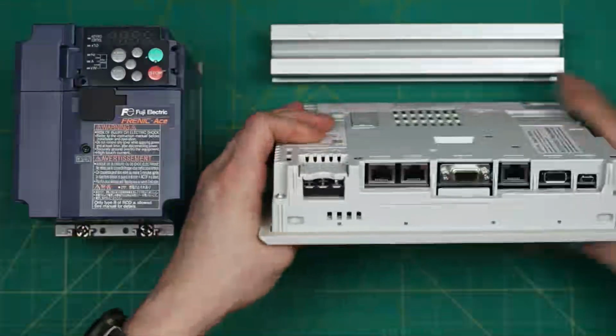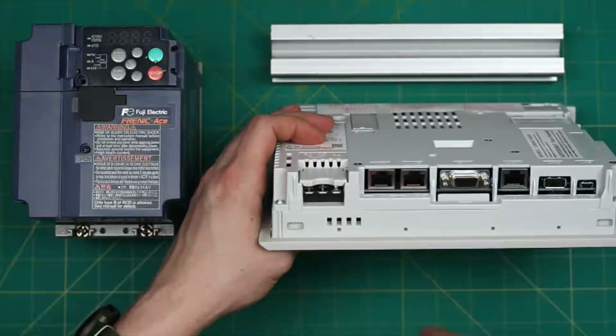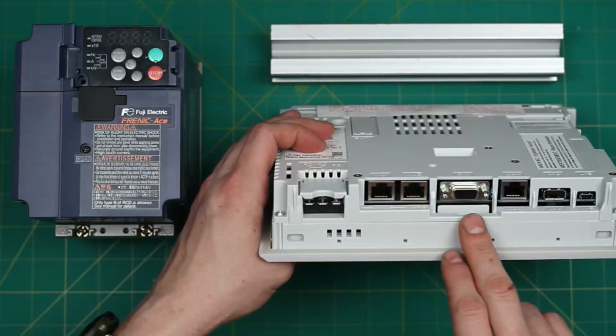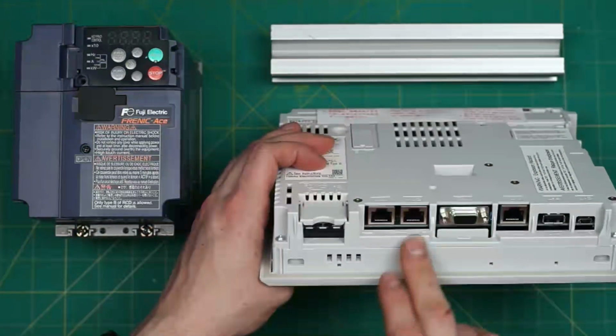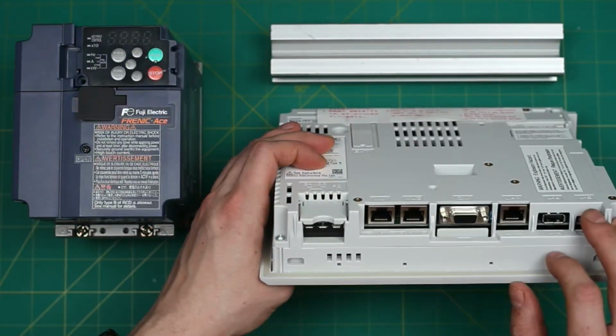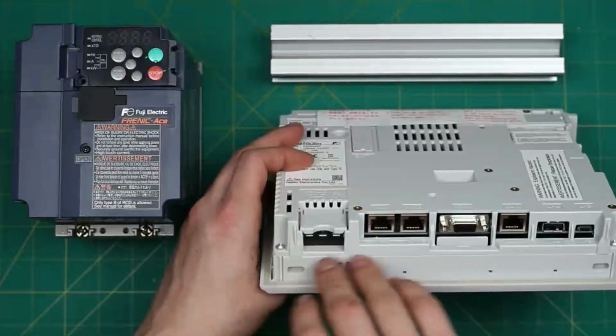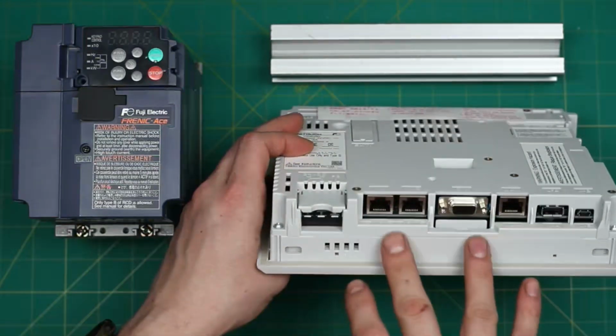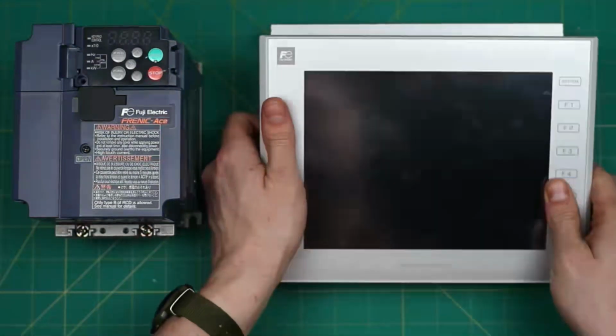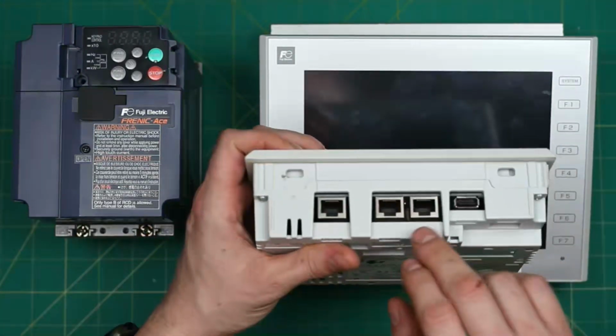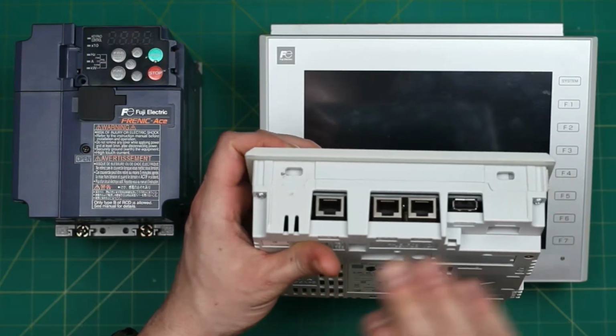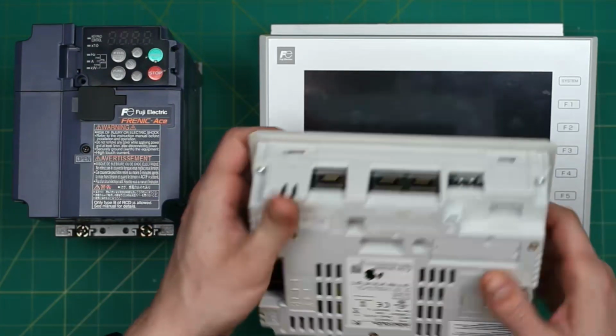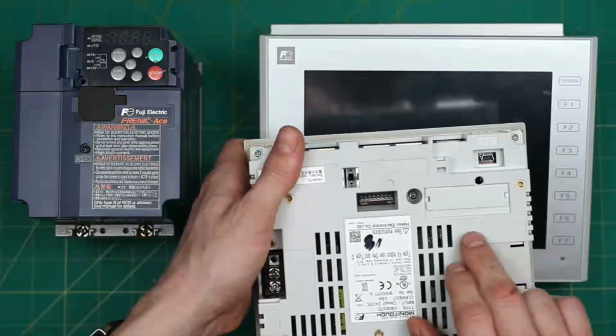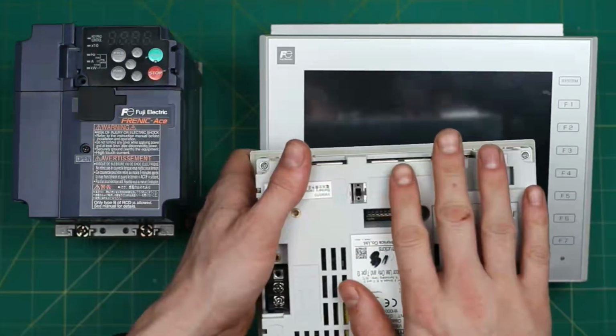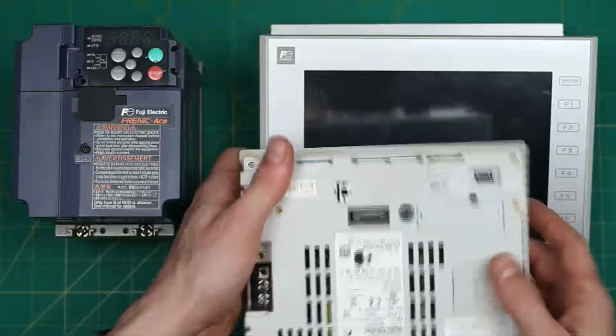on the V9 HMI we can use one of three ports: the D-sub-9 style CN1 port, or the RJ-45 style MJ1 and MJ2 ports. Keep in mind that this is the case for 8-inch and above V9 HMIs. For the 6 and 7-inch V9 HMIs, you will only find the MJ1 and MJ2 ports, not the CN1 port. However, using the EXT1 extension here, an additional port can be added to the back.